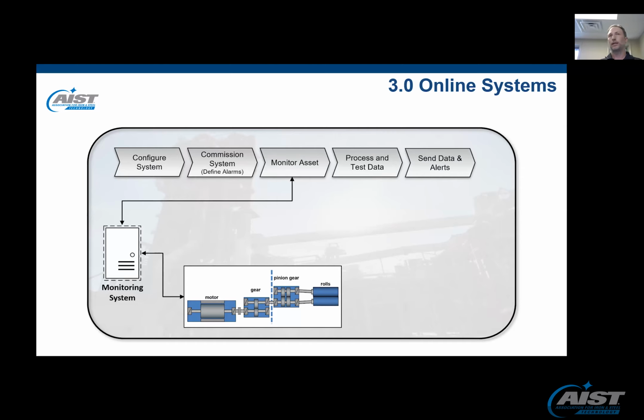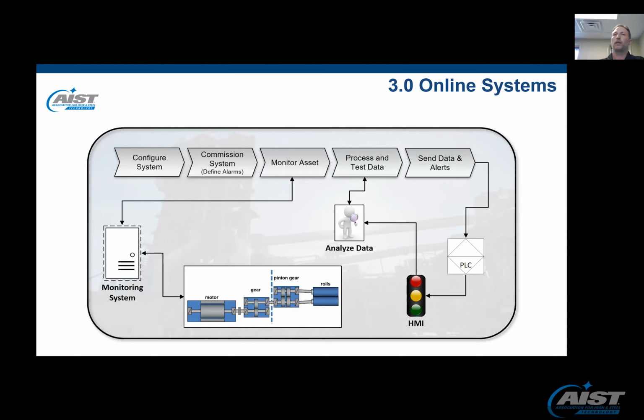We then monitor the asset. We process the data, test the data, and then send the data somewhere and also send out alerts. Typically this is tied into a PLC, with usually an HMI or something similar. The HMI then notifies an expert, who goes and analyzes the data, and based on that goes to the machine and takes corrective action. They may even go back, as the dashed line indicates, to the system and update the alarms based on what they find.